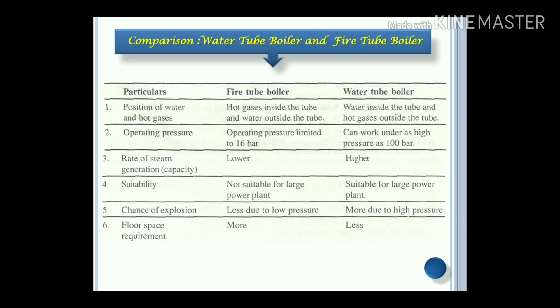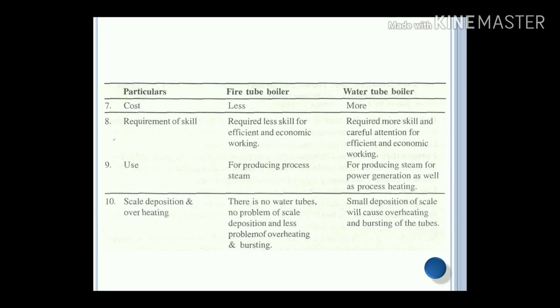Floor space requirement: in a fire tube boiler, it is more; in a water tube boiler, it is less. Cost: fire tube boiler has lower cost; water tube boiler has higher cost. Requirement of skills: in a fire tube boiler, less skill is required; in a water tube boiler, higher skill is required. As per use: fire tube boiler produces process steam, while water tube boiler produces steam for power generation as well as process heating. Scale deposition and overheating: in a fire tube boiler, there are no water tubes, so no problems of scale deposition and less problem of overheating and bursting. In a water tube boiler, even small deposition of scale can cause overheating.